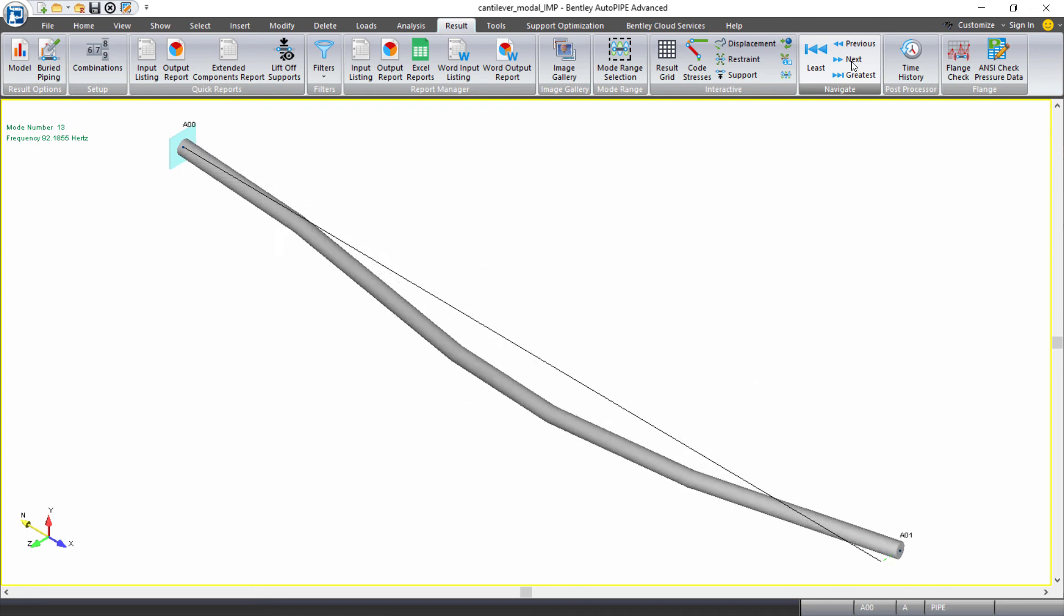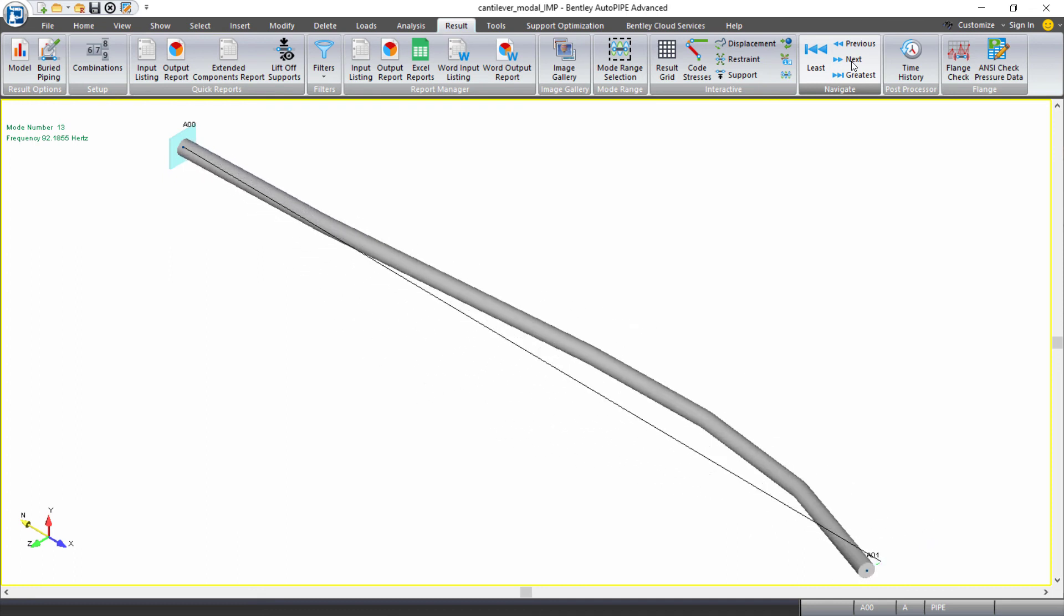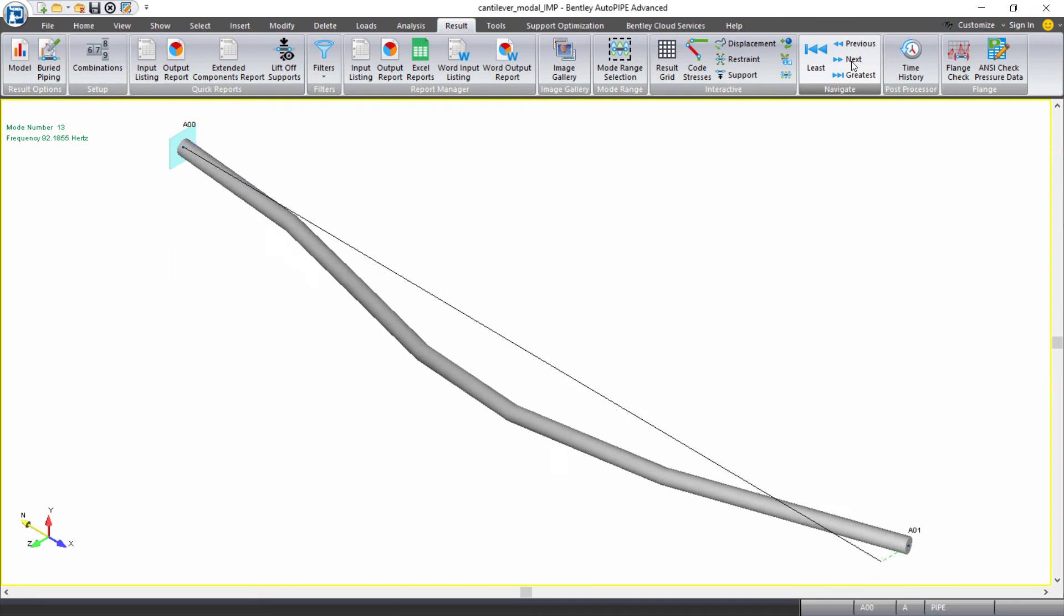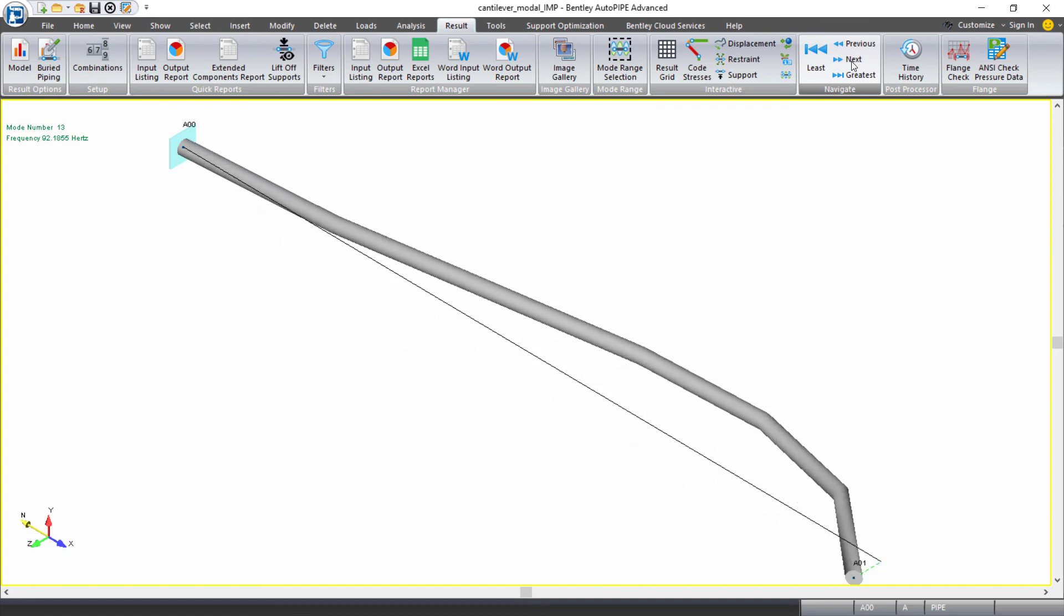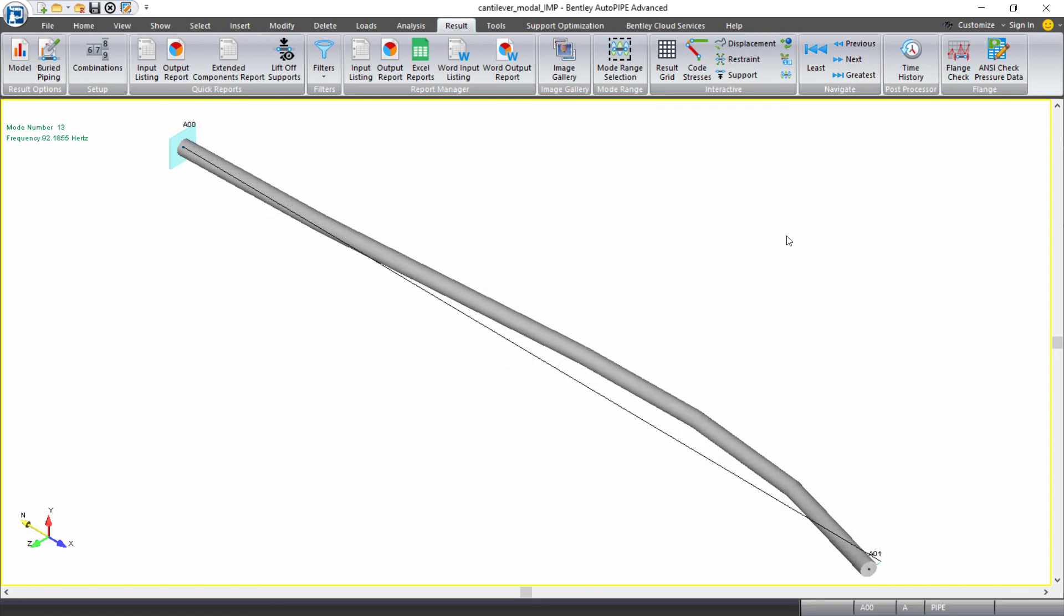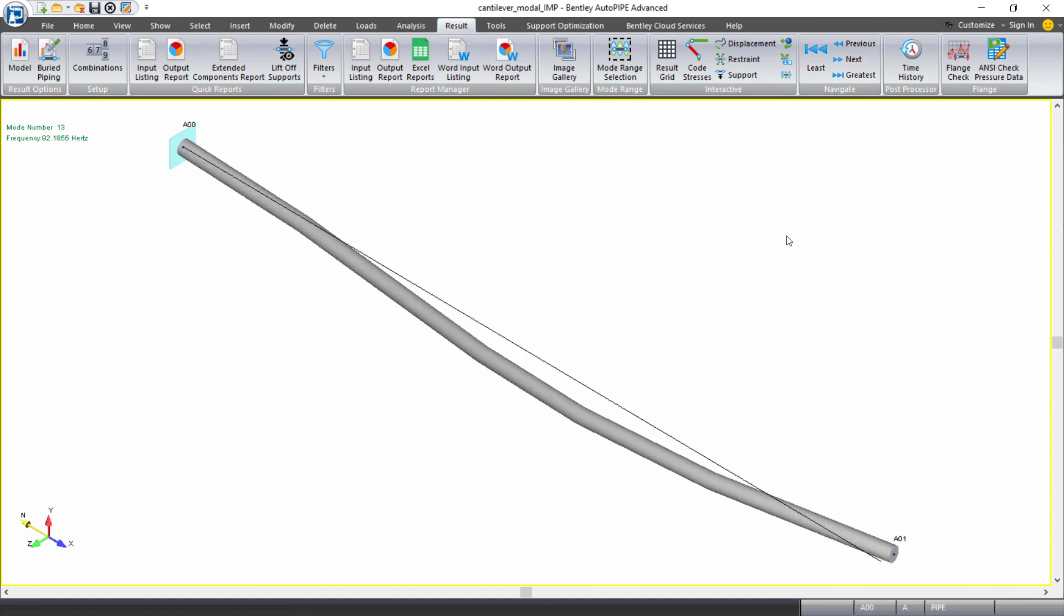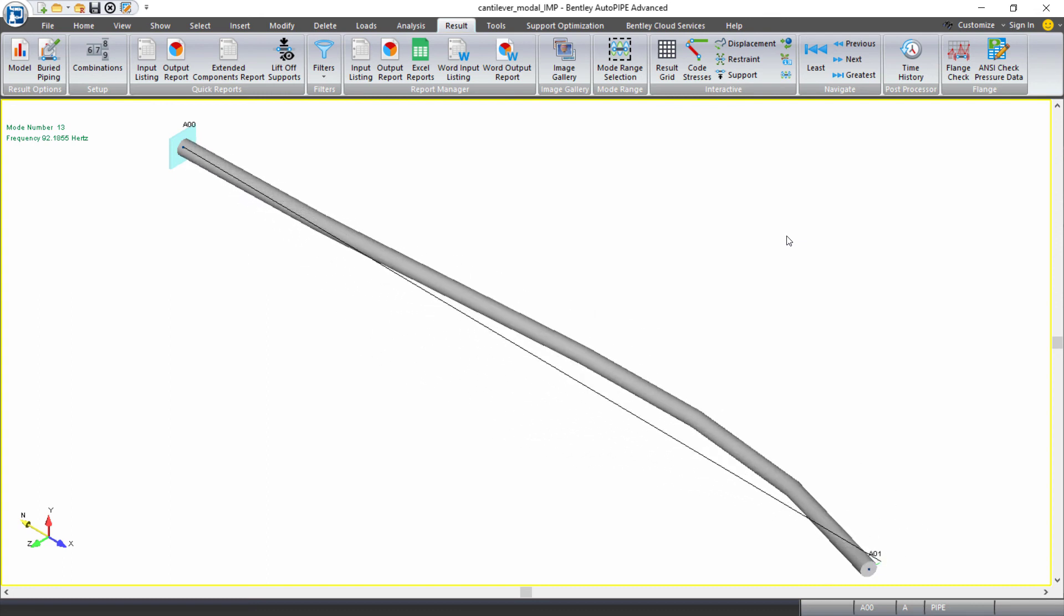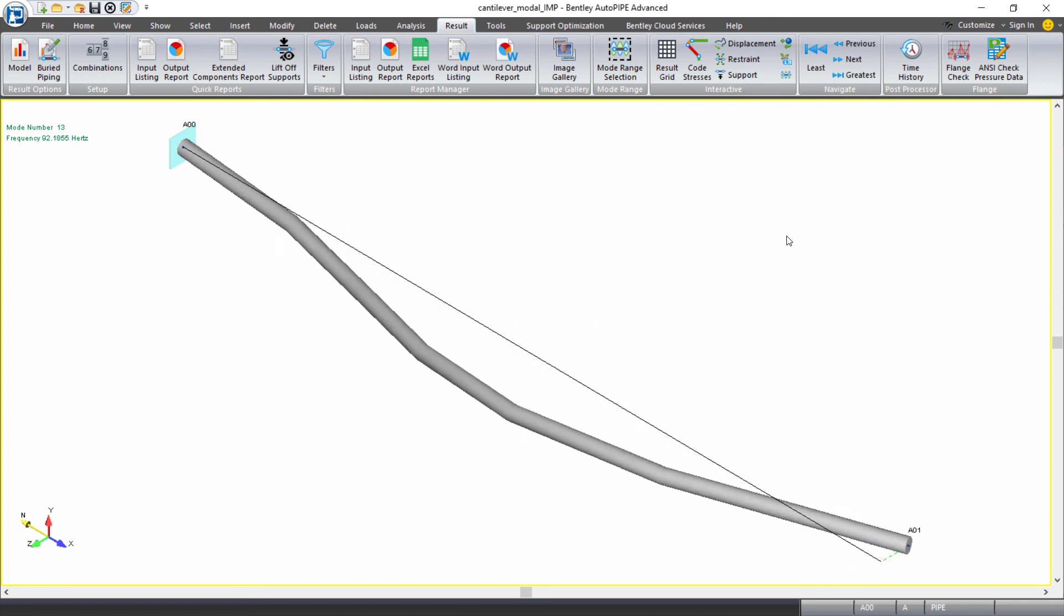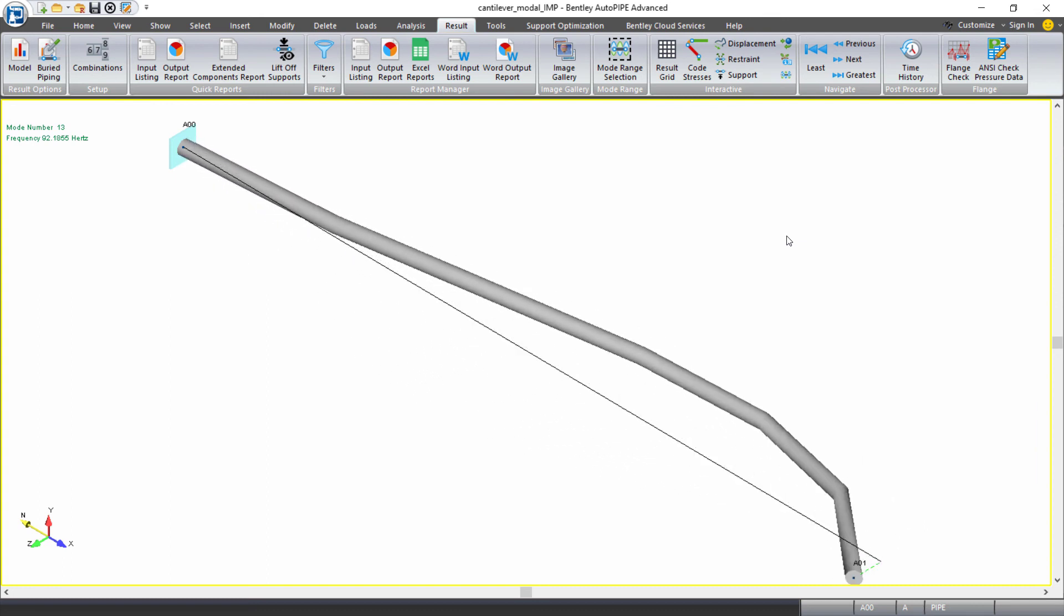So although AutoPIPE is reporting to us 13 modes, we actually have seven frequencies that we expect to produce a response from our piping system between 0 and 100 hertz now that we've refined our model.